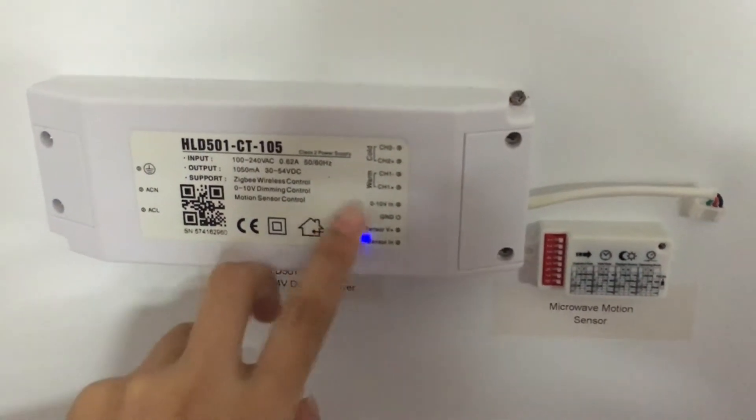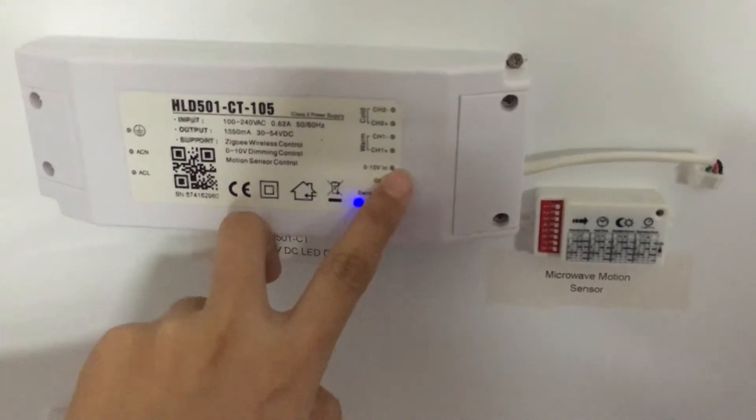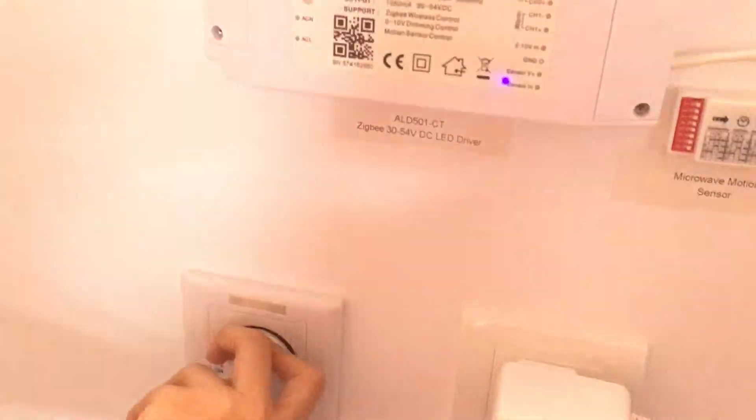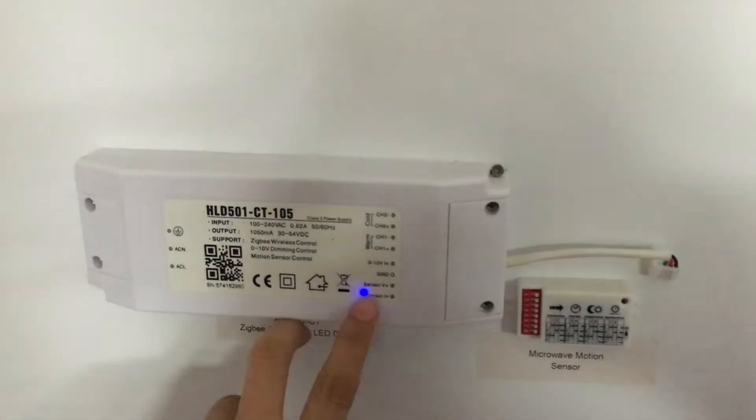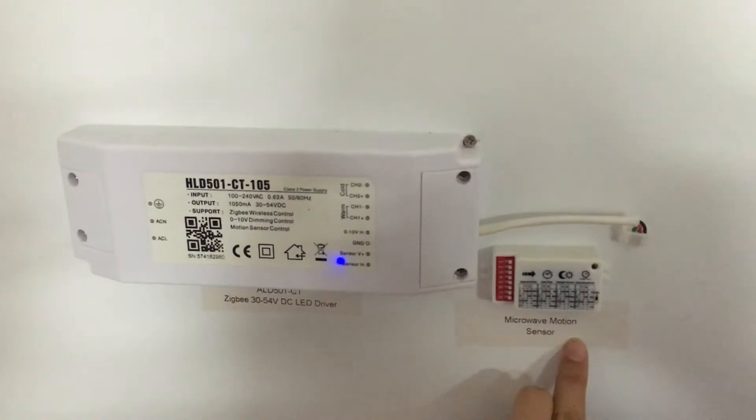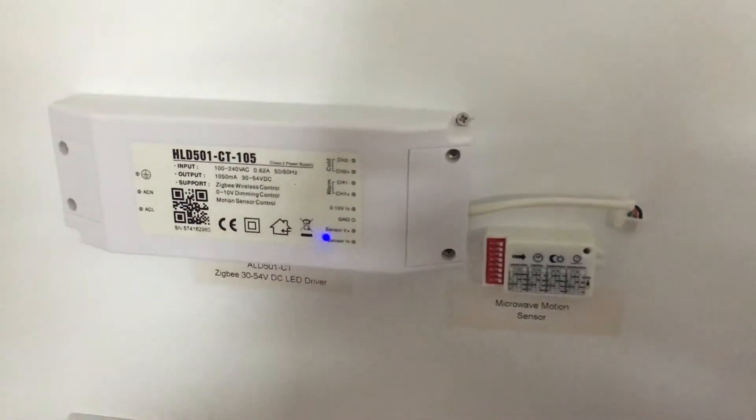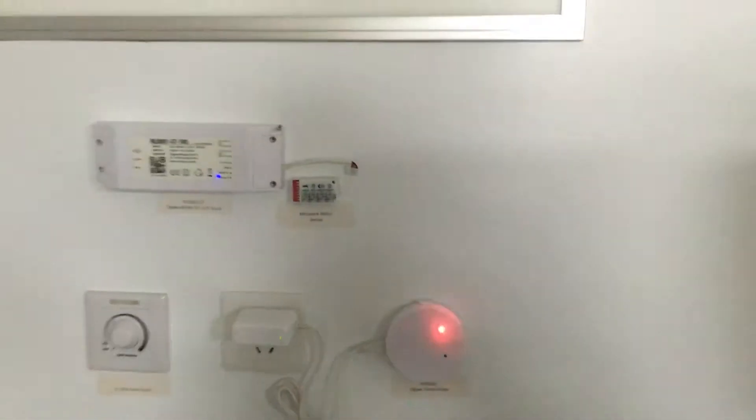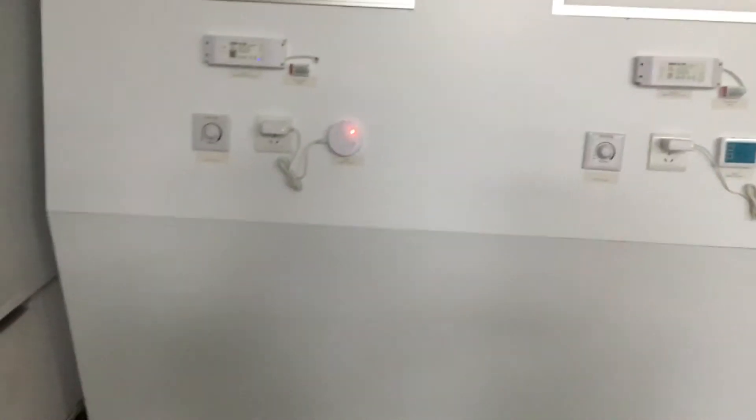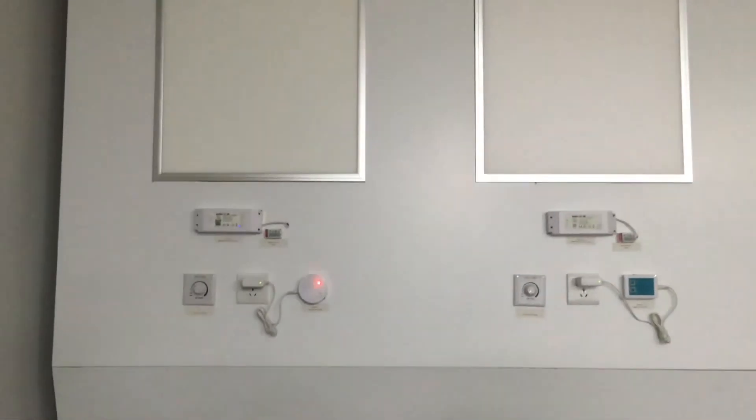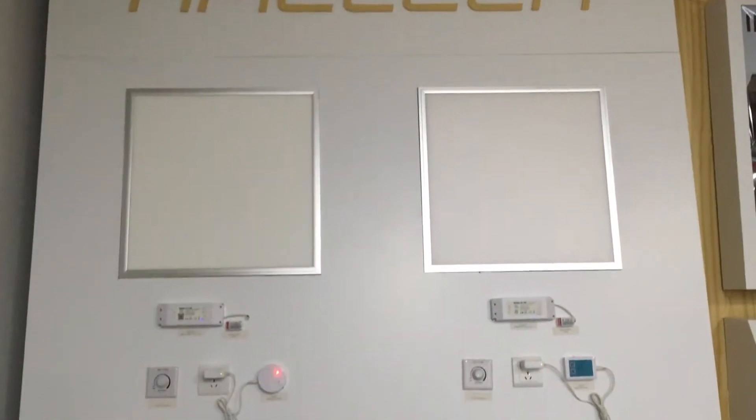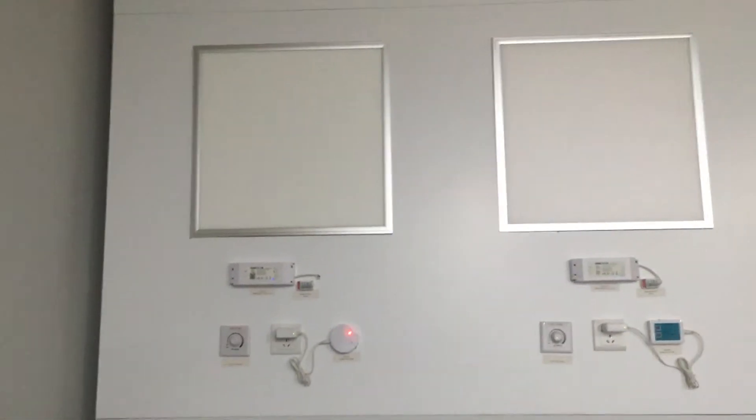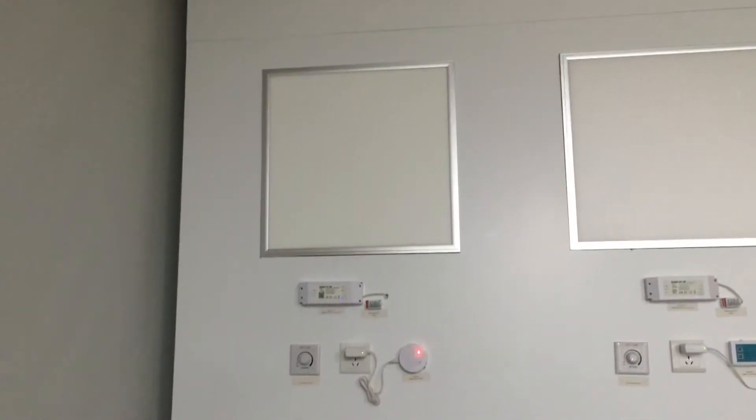There's 0 to 10 volt input which can adapt to common 0 to 10 volt dimmer switch control. Now here's the sensor input which can work together with the microwave sensor. So all together Zigbee wireless control, 0 to 10 volt control, microwave sensor control. All together to realize really automatic control over the panels.